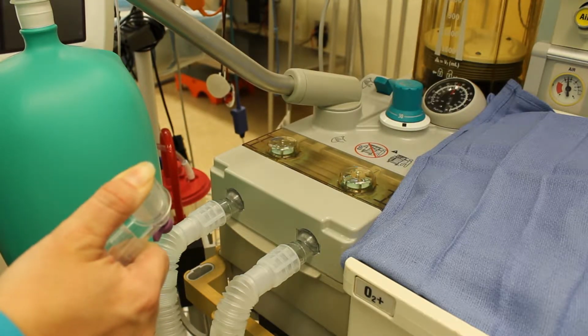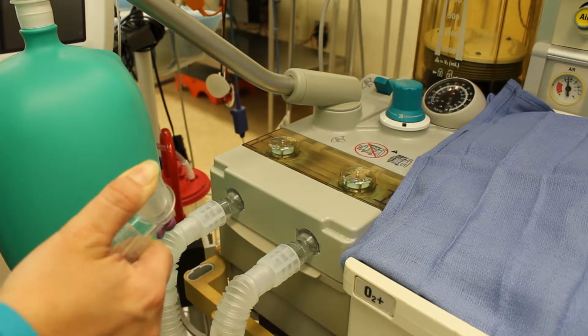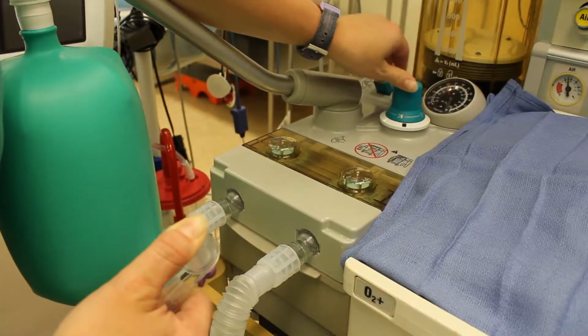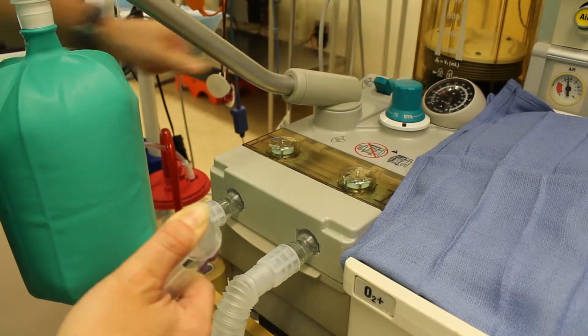Release the flush valve, turn each vaporizer on and off, and make sure that the circuit pressure continues to remain at or near 30 centimeters of water. Fully open the APL valve and make sure that circuit pressure quickly returns to zero.